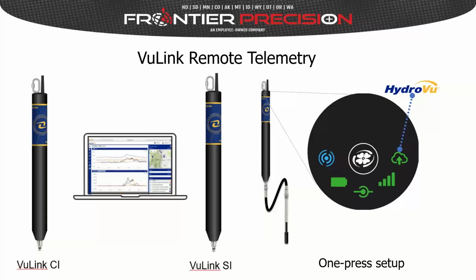Both of these are battery powered with either alkaline or lithium D batteries, and we're talking battery lives of years on this. And you can set these up so that they will send you a text message on an alarm condition. So you could specify, hey, in my pond, if dissolved oxygen goes below 4.5 milligrams per liter, I want to get a text message telling me that. So you can set that up on the VuLink transmitter, as well as you can have it just push data to a cloud-hosted software program called HydroVu. So you can have it logging data like every hour, and then once or twice a day, you can push data to this cloud-hosted HydroVu program.